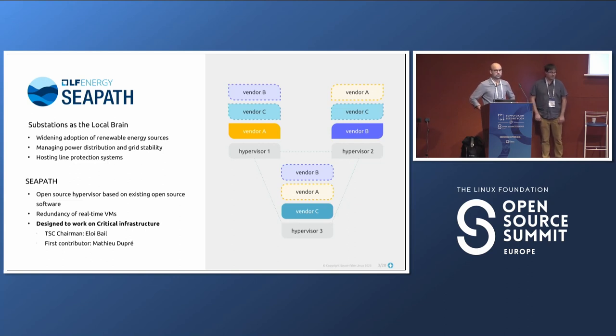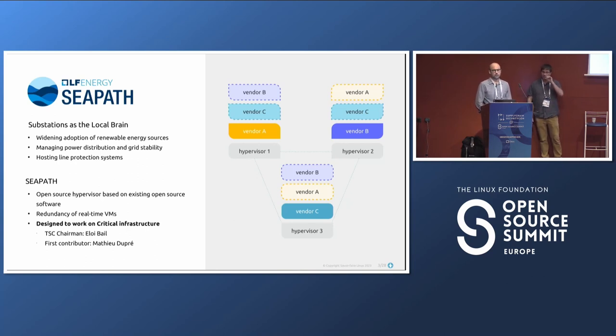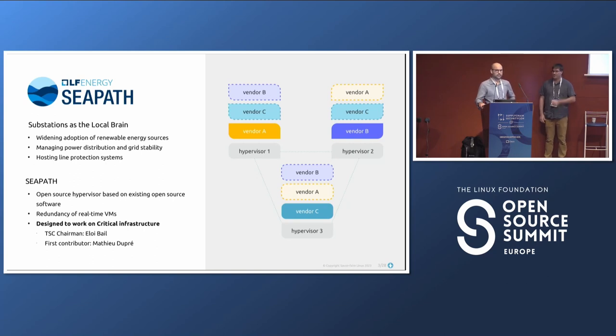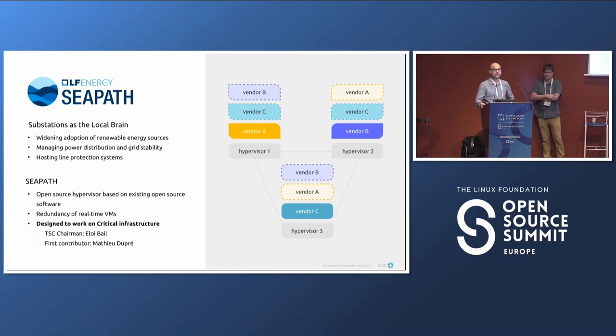We use virtualization because we want a multi-vendor approach — the idea is to have different companies' products working together on the same hypervisor. Virtualization helps integrate third-party solutions, which could be Linux systems but also non-Linux systems for logging, monitoring, and so on. There are some weaknesses regarding performance, real-time, and network latency, but we've done analysis and can achieve the performance expectations for protection systems. Using VMs also allows clearly separating different vendors' software.